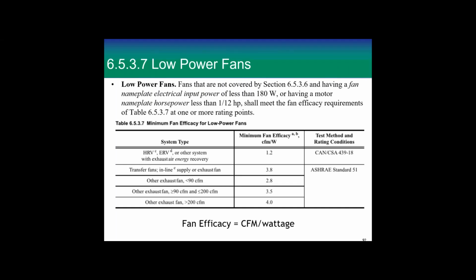Lower power fans that are not covered by section 6.5.3.6 and having a fan nameplate electrical input power of less than 180 watts, or having a motor nameplate horsepower of less than 1/12 horsepower, shall meet the fan efficacy requirements of this table. Here's a fan efficacy. Now, these are small fans. These are little fans, and they're not going to move your needle at all in your building problem. But there's a whole lot of them in the world, and the people that are involved with these small fans put this forward as a change to the standard. And it does save some energy, but it's really little numbers per fan or per your job problem. But there they are.